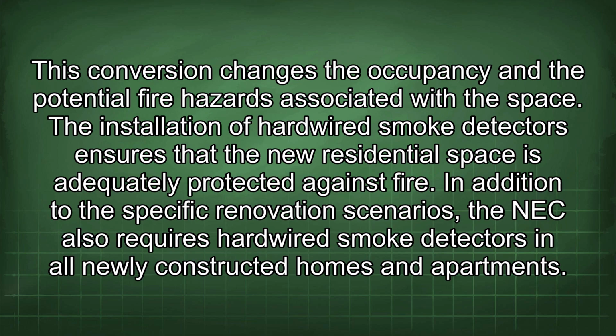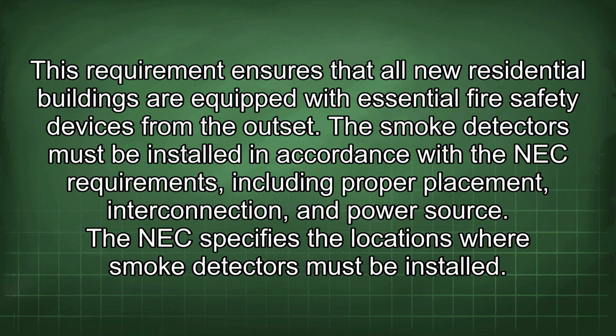This conversion changes the occupancy and the potential fire hazards associated with the space. The installation of hardwired smoke detectors ensures that the new residential space is adequately protected against fire. In addition to the specific renovation scenarios, the NEC also requires hardwired smoke detectors in all newly constructed homes and apartments. This requirement ensures that all new residential buildings are equipped with essential fire safety devices from the outset. The smoke detectors must be installed in accordance with the NEC requirements, including proper placement, interconnection, and power source.